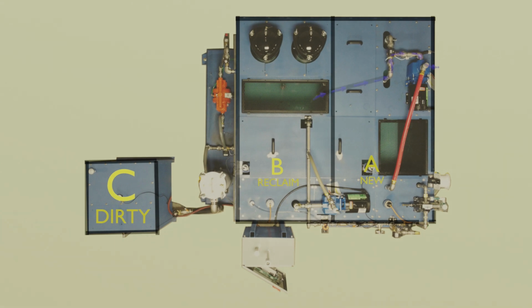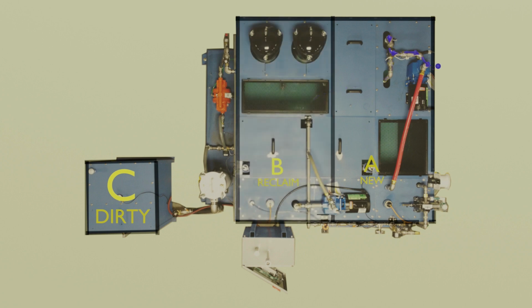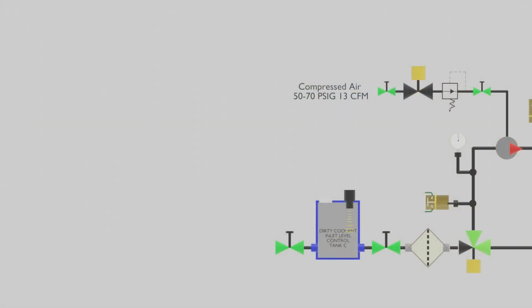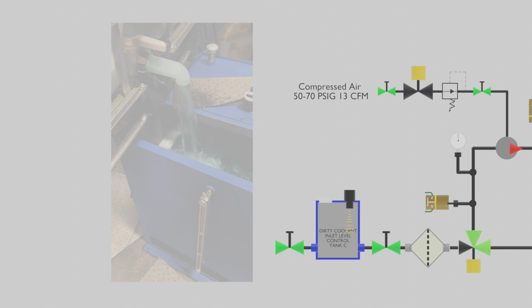Tank B Reclaim is the default customer coolant supply, unless its level is too low or the coolant concentration value is out of specification. When this happens, Tank A becomes the default supply until that is rectified. For a more detailed understanding of the Tank B reclaim process, please follow along with the following animated schematic.